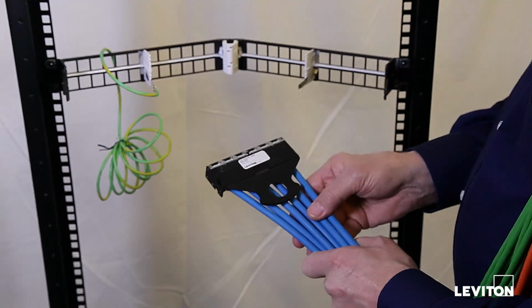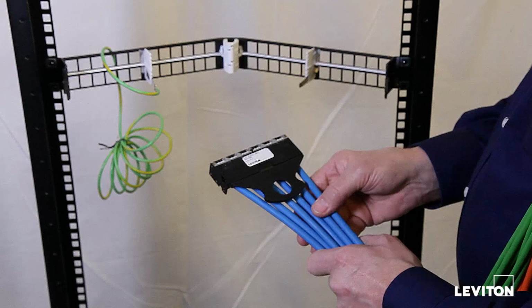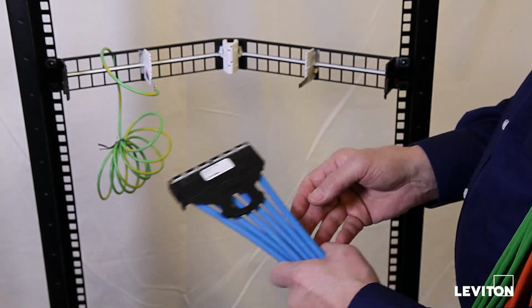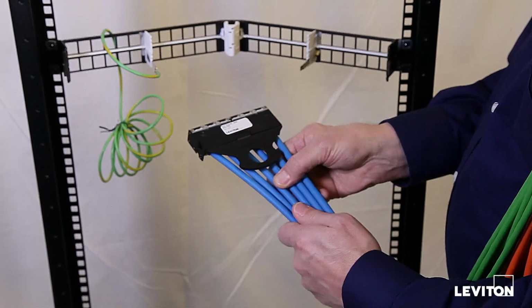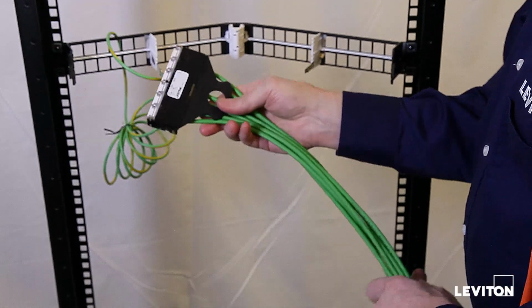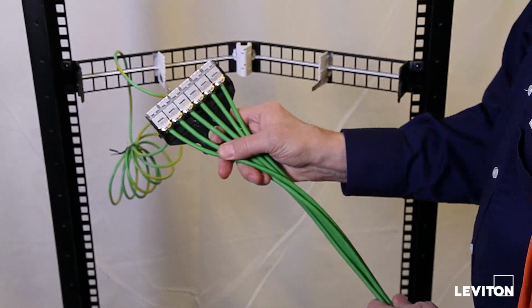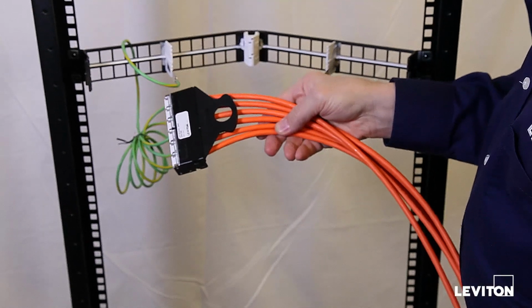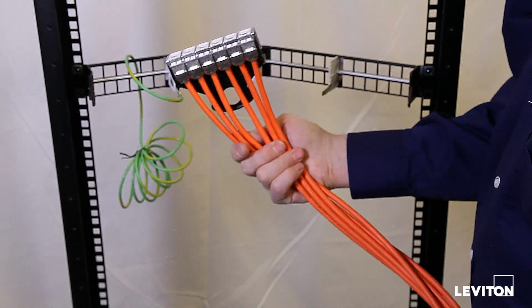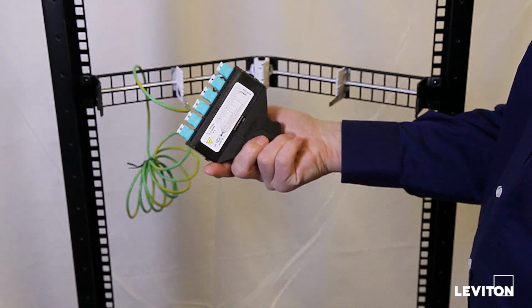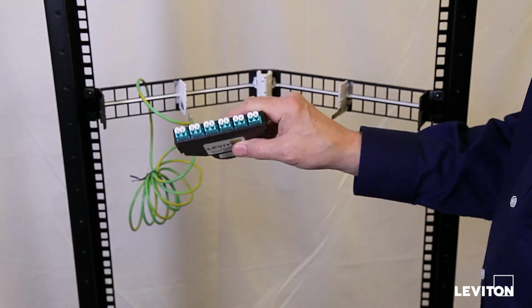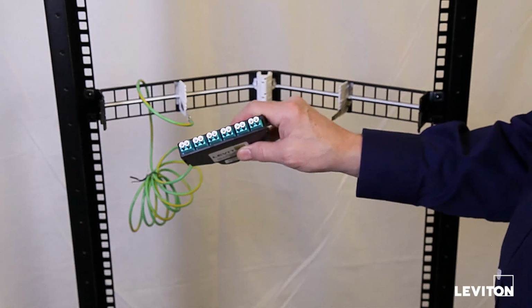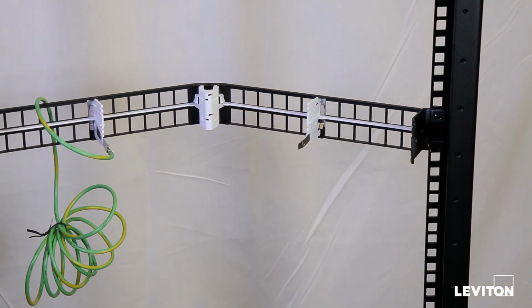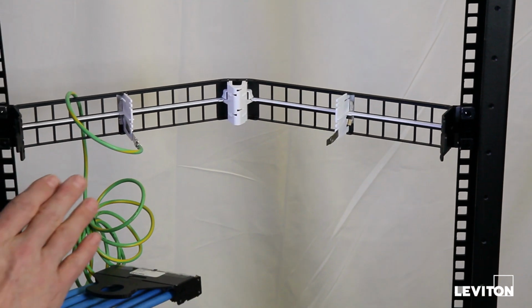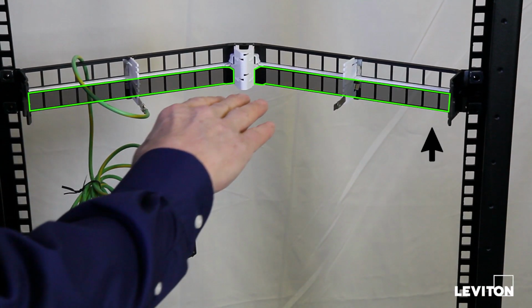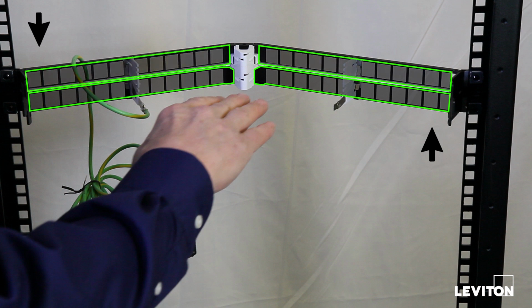To demonstrate how to load E2XHD angled and flat panels, we'll use cassettes loaded with 3 types of Category 6A cables. Unshielded Euroclass DCA Category 6A cable, shielded Euroclass CCA Category 6A zone cable, and Euroclass B2CA shielded Category 6A cable. The panels can also accommodate fiber optic loaded cassettes like this one, which would break out from an MTP connector to 6 duplex LC fiber connections. When routing cable up from a raised floor to an angled or flat panel, insert the cassettes into the bottom row first. When routing cabling down from the ceiling, insert the cassettes into the top row first.